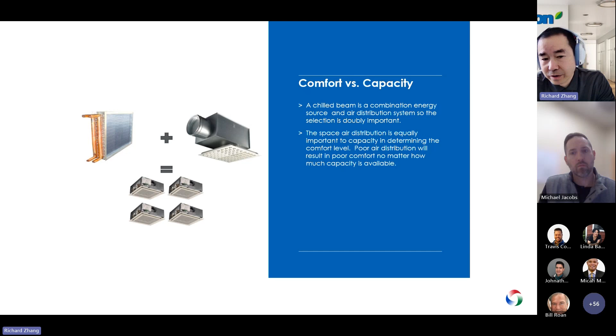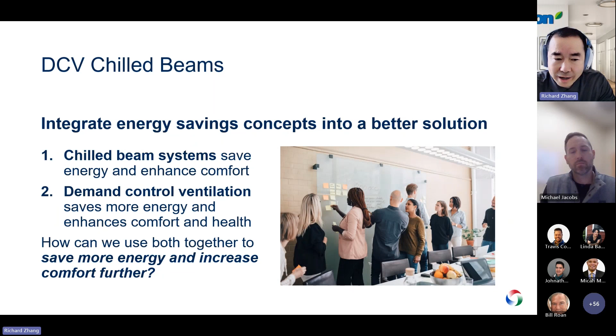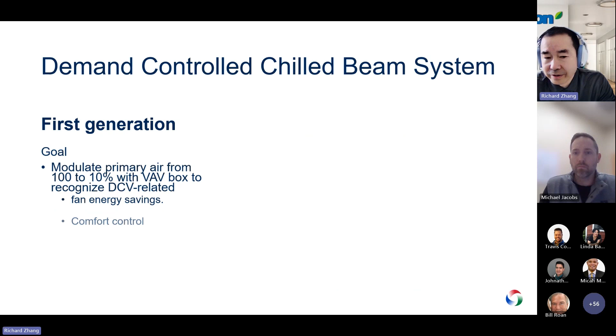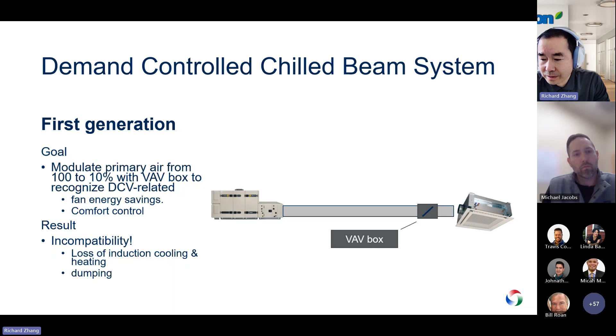So with the trend, there's a lot of push for demand control systems, and chill beam can be a great candidate for saving energy. Then people, including many leading consulting firms, began to think, how can we marry those two best energy saving technologies together to save more energy? One of the tries is to put a VAV box in front of a constant airflow chill beam. You know what happened? The result is that they're incompatible. They lost the induction and consequently they are losing the cooling and heating capacity. So that's the capacity side of the story. On the other hand, they lost the velocity and then they lost the Coanda effect, and the chill beam will basically pretty much dump the air into the space.